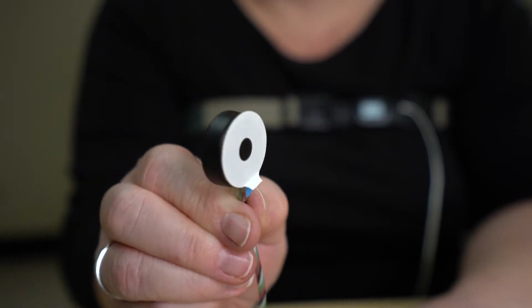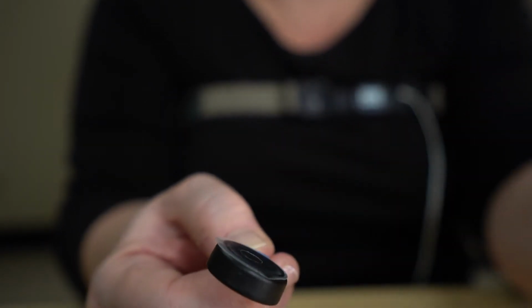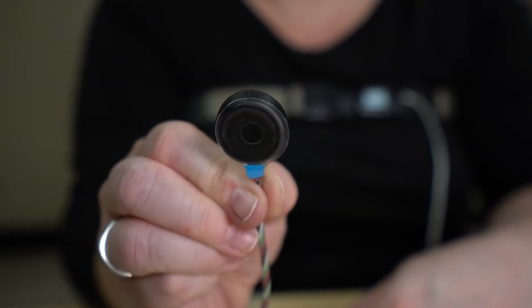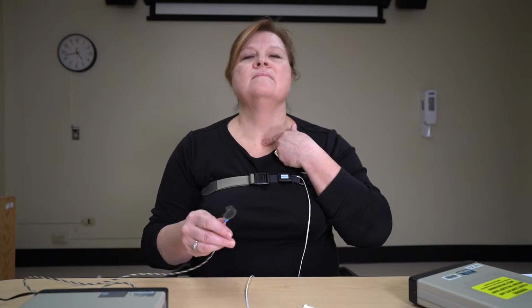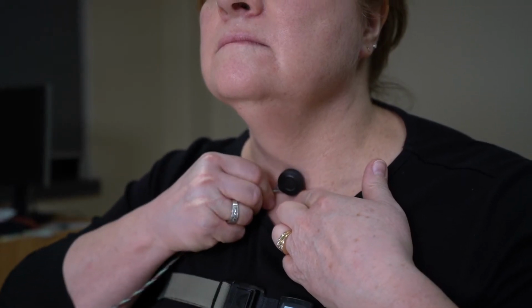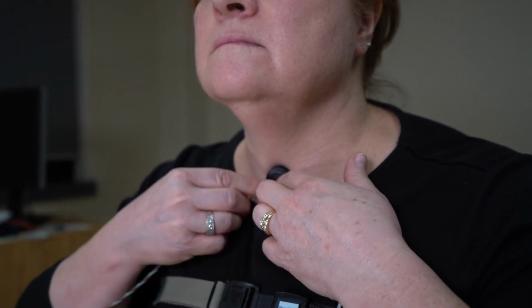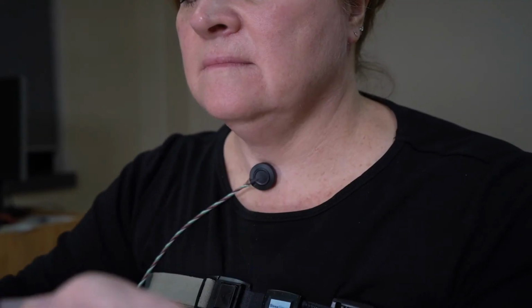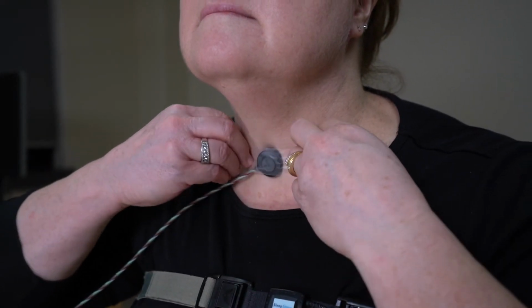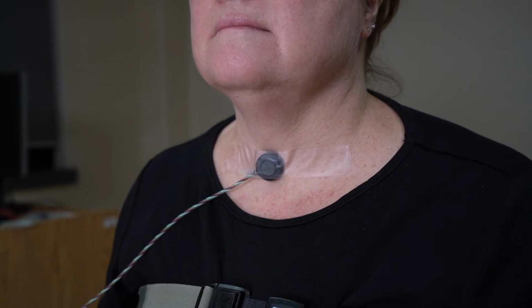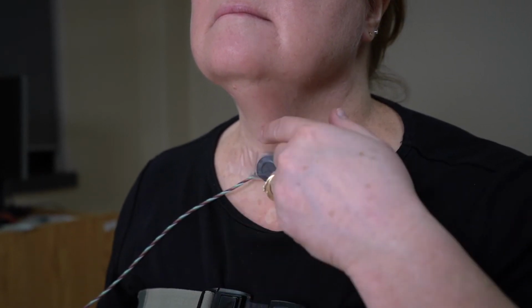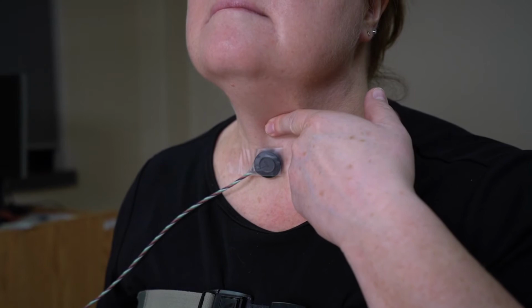To attach the Snore Sensor to your neck, peel off the wax paper to expose the adhesive. Apply the Snore Sensor about 1 finger above the bony sternal notch, below the Adam's apple, with the cord running down or slightly offset to one side. Secure the sensor by taping it onto your neck. Remember, it must be placed on a soft spot at the base of your neck, not on the breastbone or not on the Adam's apple.